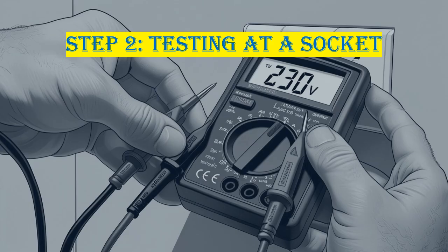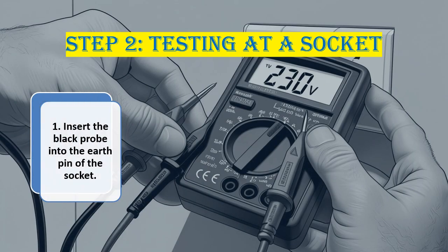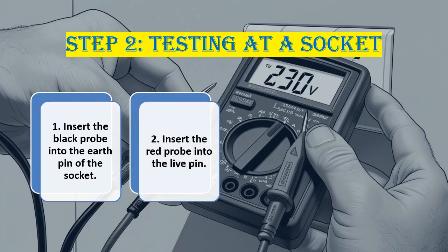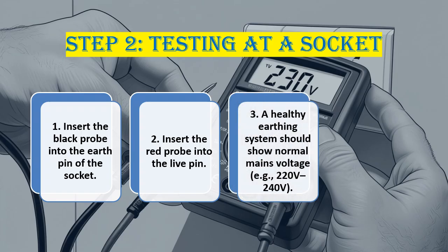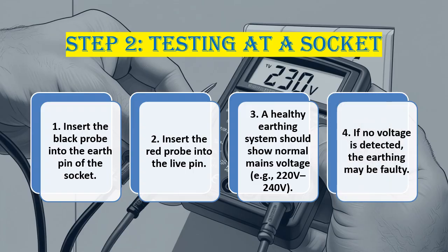Step 2: Testing at a socket. Now, test earthing at a wall socket. Place the black probe into the earth pin and the red probe into the live pin. If earthing is proper, the multimeter should display the normal mains voltage, typically between 220 and 240 volts. If no voltage is detected, it may indicate a faulty or missing earthing connection.